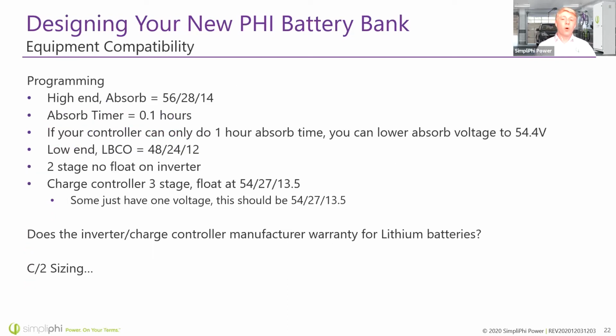As far as equipment compatibility, before purchasing your system or after, make sure that the equipment you're going to connect it to is compatible. So our batteries need to absorb at 56 volts for the 48 volt version, 28 volts for the 24 volt version, or 14 volts for the 12 volt version. I want to make sure that's clear. So the absorb timer also should be set. That's going to be 6 minutes.